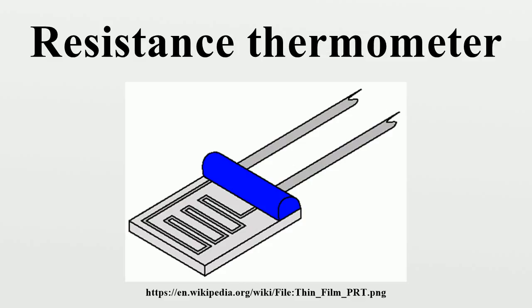Wire wound elements can have greater accuracy, especially for wide temperature ranges. The coil diameter provides a compromise between mechanical stability and allowing expansion of the wire to minimize strain and consequential drift. The sensing wire is wrapped around an insulating mandrel or core. The winding core can be round or flat but must be an electrical insulator. The coefficient of thermal expansion of the winding core material is matched to the sensing wire to minimize any mechanical strain. This strain on the element wire will result in a thermal measurement error.